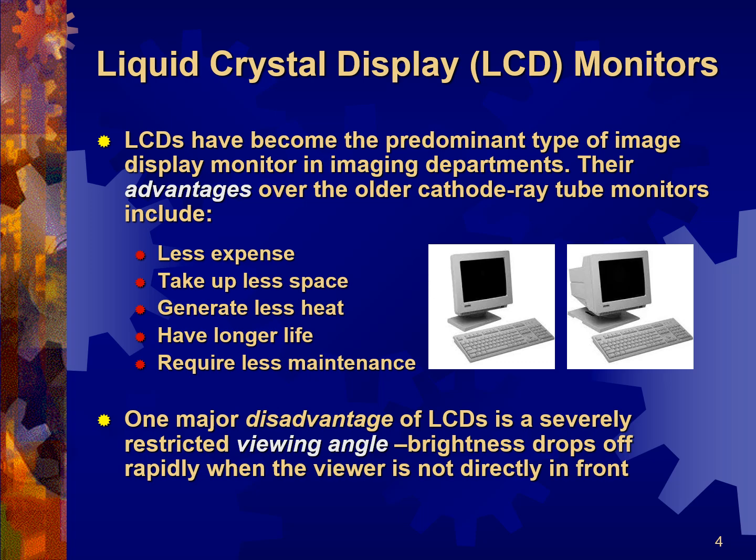They are seeing, first of all, a geometrically distorted image from their acute angle. Second of all, something that's about 60% dimmer than it's actually supposed to look like as far as registering in their field of view. So they have no idea. That's not real QC.